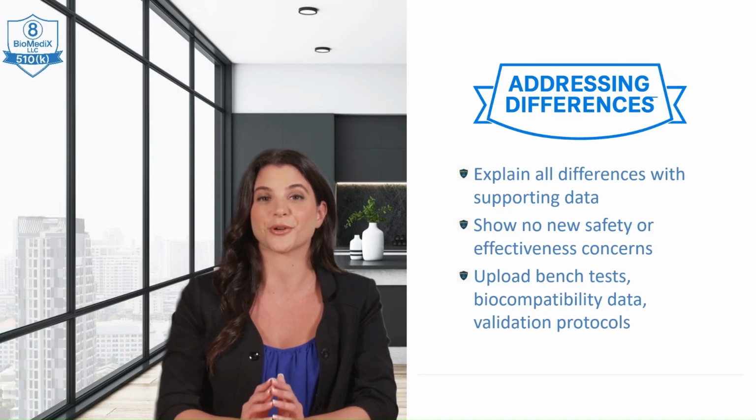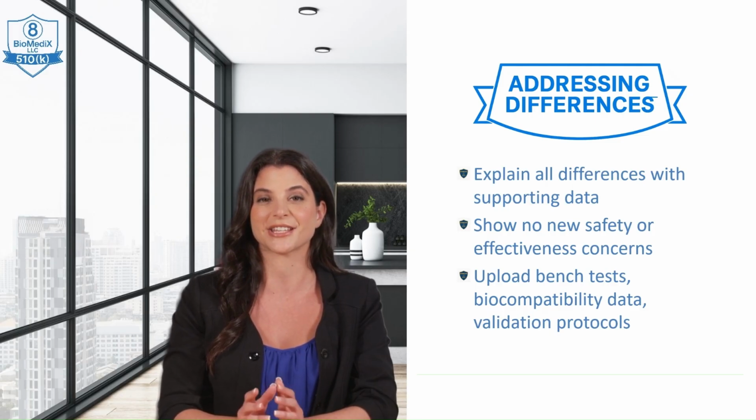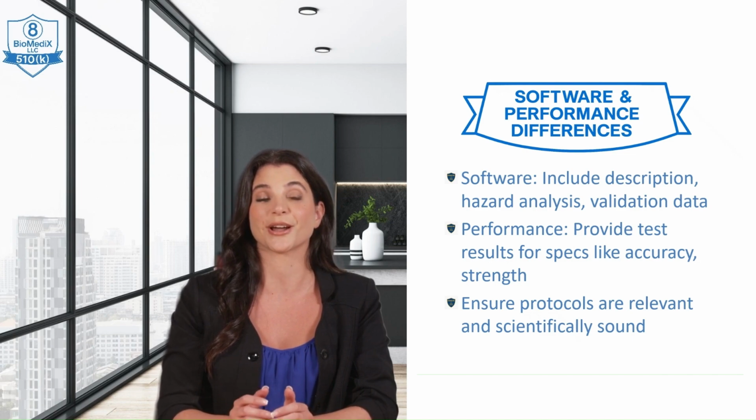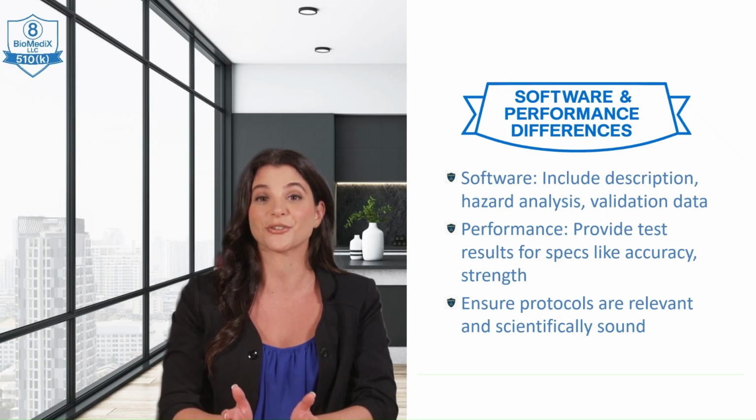If design or performance specifications differ, provide performance testing data to demonstrate equivalent performance. Ensure your testing protocols and acceptance criteria are scientifically sound and relevant to the device's intended use. For software differences, a detailed software description, hazard analysis, and validation documentation will be critical.